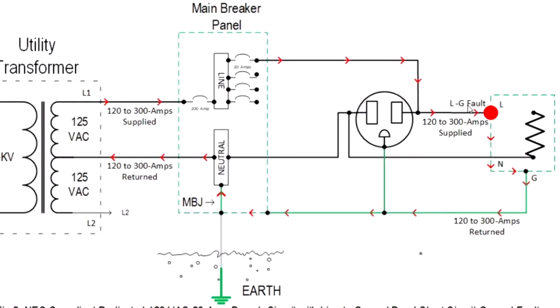Now, the reason I know this is from working with the NEC for 6 years and working with the codes for 30 in practice. It takes 120 amps to induce enough fault current to trip a 20 amp breaker within half a cycle. So in other words, for a breaker rating, you want at least enough fault current to be 6 times the rated current. In this case, 20 amps times 6 is 120 amps.